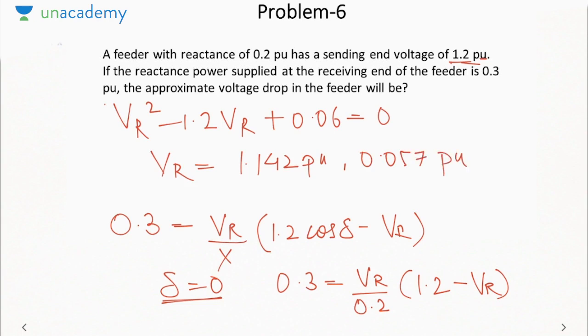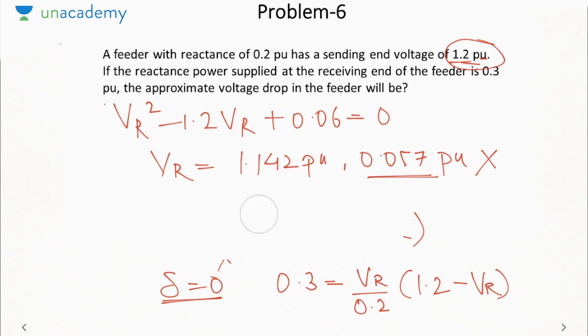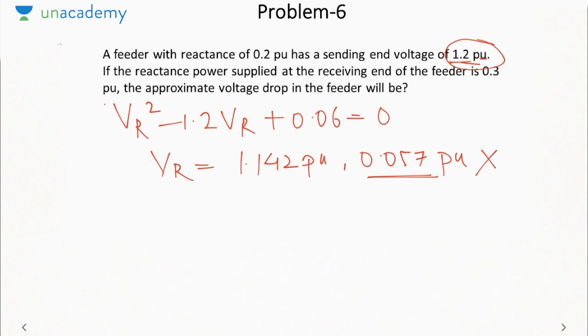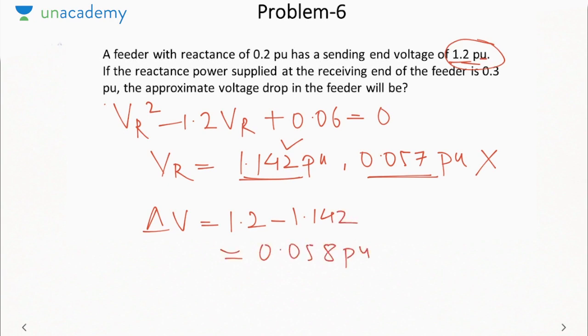But now sending end voltage is 1.2 pu. So receiving end should be close to that. So this is an impractical value. There cannot be such a high voltage drop in a transmission line. So we will take Vr equal to 1.142 pu. So voltage drop will be 1.2 minus 1.142, which is almost 0.058 pu. Okay, so this will be the voltage drop between the sending and the receiving end.